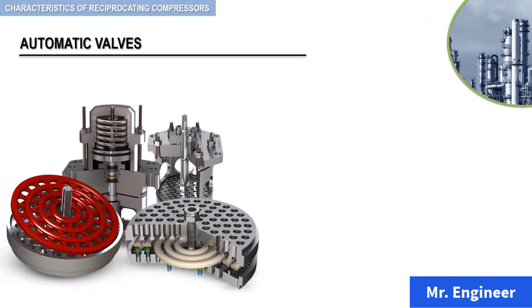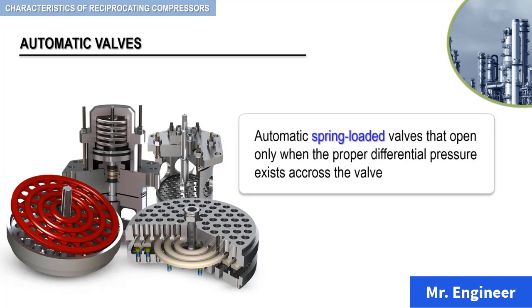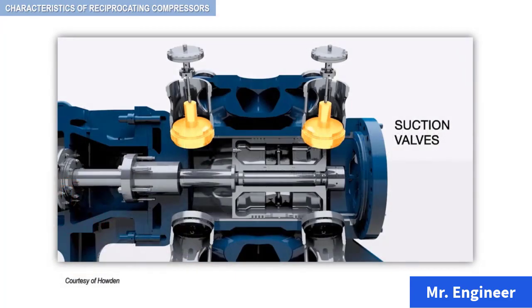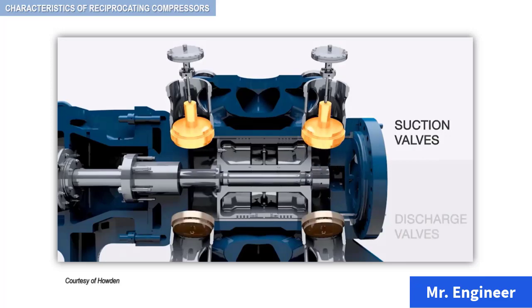The reciprocating compressor uses automatic spring-loaded valves as the ones you can see here that open only when the proper differential pressure exists across the valve. This was discussed in a previous video, but is reminded here using the following simplified 3D animation depicting a double-acting cylinder.